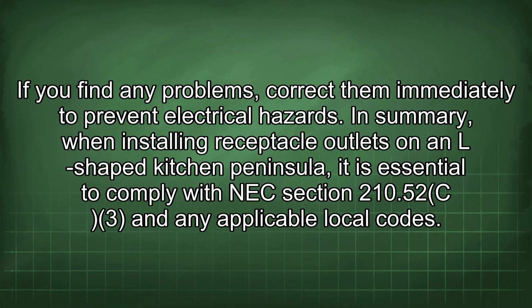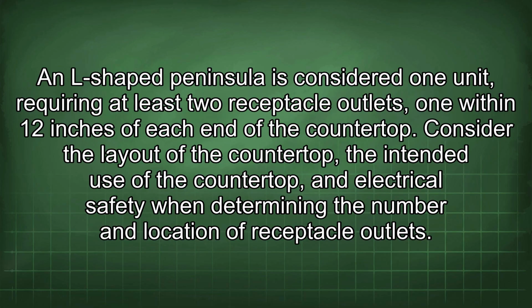In summary, when installing receptacle outlets on an L-shaped kitchen peninsula, it is essential to comply with NEC Section 210.52(C)(3) and any applicable local codes. An L-shaped peninsula is considered one unit, requiring at least 2 receptacle outlets, one within 12 inches of each end of the countertop. Consider the layout of the countertop, the intended use of the countertop, and electrical safety when determining the number and location of receptacle outlets.